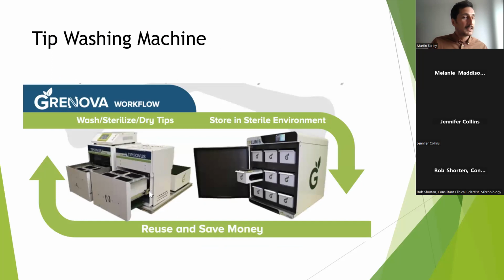This is more maybe a teaching setting, by the way. I think I heard somebody mention teaching. These are tip washers. They will wash tips in recognition that we use a lot of tips. Sorry. Oh, I should mute that. But they wash tips. We bought this at UCL to pilot it, and you know, if you trust the marketing material, you would save a ton of carbon immediately after several washes. But that's not the truth. The truth is you don't do that. So you have to use it several thousand times to get a carbon saving, which is okay. You know, sometimes we do go through that volume.